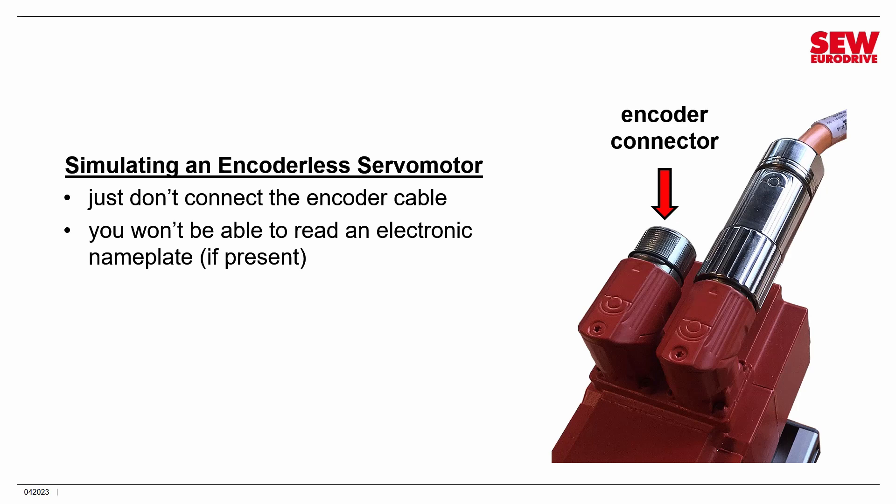It basically is the equivalent of the physical nameplate on the motor, which means the VFD can read the motor's parameters and more or less do an automatic setup. It's not quite as exciting as DDI, which we talked about earlier. It's kind of an earlier-generation idea that you can do sort of a plug-and-play motor.